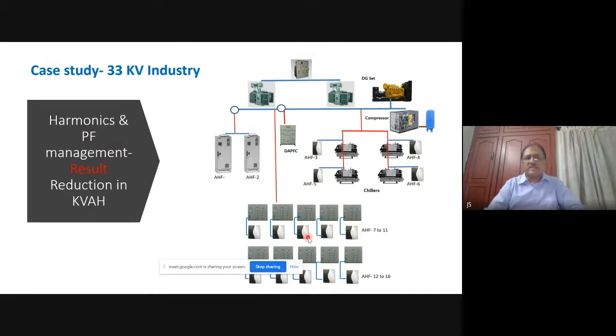I'm also using a case study which we successfully implemented in 2015 in Andhra Pradesh, where, as you know, we have this kVAH billing. This was a multinational FMCG company, and this company had 33 kV supply coming from the grid. They had a detuned APFC already installed in their plant. But what happened was they had frequent failures of PCBs. So the approach of the customer to us was to basically address the PCB failure and give them relief from that failure, because this was causing a lot of production losses. So they had 4 chillers, they had a compressor, a standby generator, and 10 MCCs.